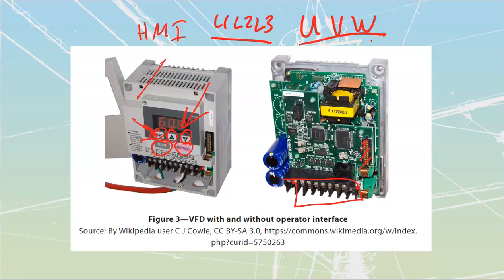I have seen more VFDs destroyed by people putting power into U, V, W and trying to take it off L1, L2, L3 than by any other method that you as electricians are going to find to destroy these drives. And it's a simple issue. Just read the manual that came with it. If you get a VFD, it's going to come in a box, and when you unpack the box, it's going to have a manual. You're going to flip through that manual until you find the associated drawing for these things.